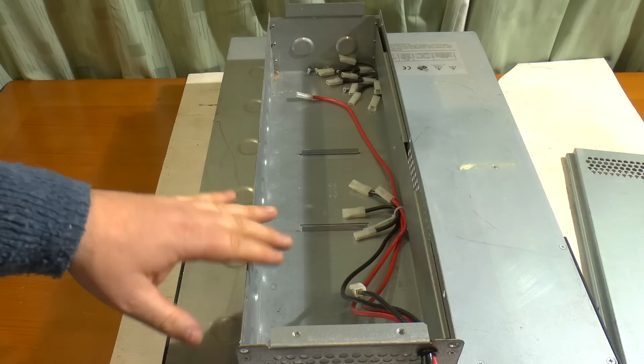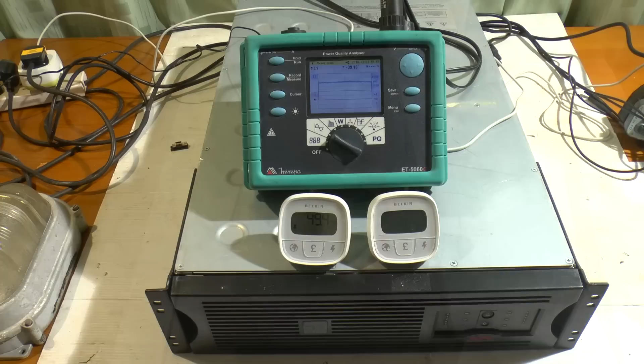Custom microprocessor, Philips branded this time. Apart from that, it's broadly the same as the other one. You get these strangely tall electrolytic capacitors here, the set of 4 heat sinks with the connections going off to the transformers in parallel this time rather than in series, and that's about it. 2 more things. The part number of this one is SU2200 RMXLI 3U, and the battery compartment, as you can see inside, it actually runs the batteries as 2 sets of 4, so it's still a 48 volt supply. It's just got 4 batteries in parallel with another 4 batteries.